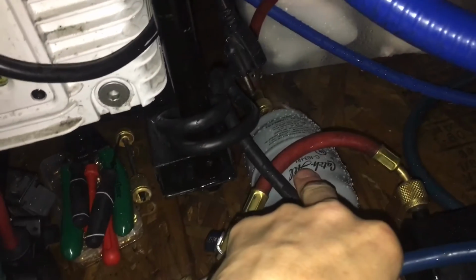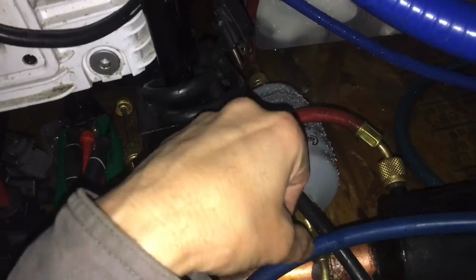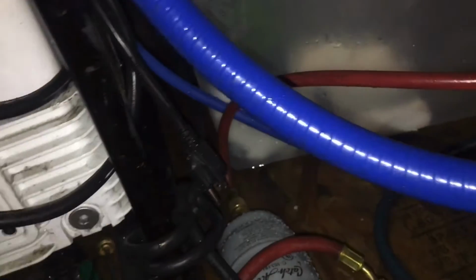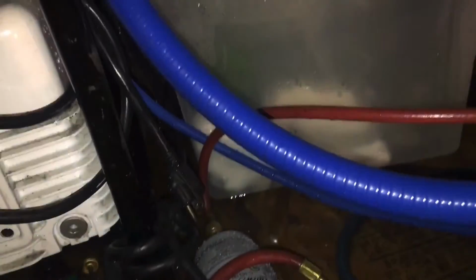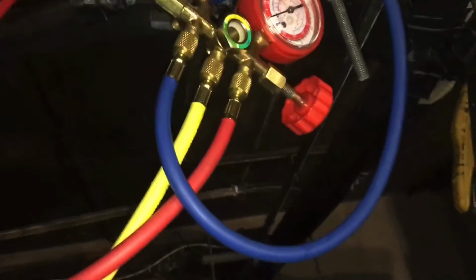Now, when I go to put this refrigerant back into the system, I will get a brand new HH liquid side filter that hasn't been used. I will hook it up to the system. I will pull a vacuum on the filter and the line down to roughly, say, 60 or 100 microns. And then I will open up the liquid side to fill the system. And I'll make another video after this. Oh, you gotta remember, this was the system in my earlier released video.